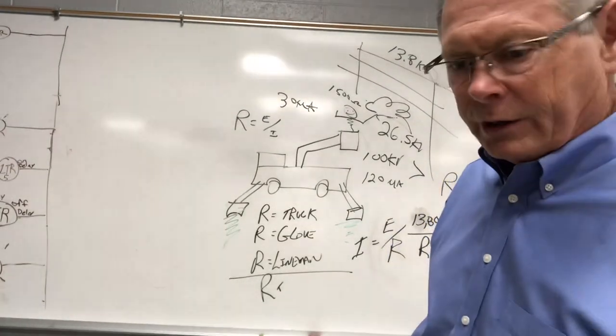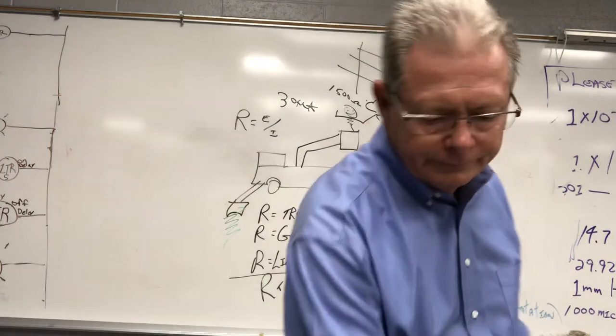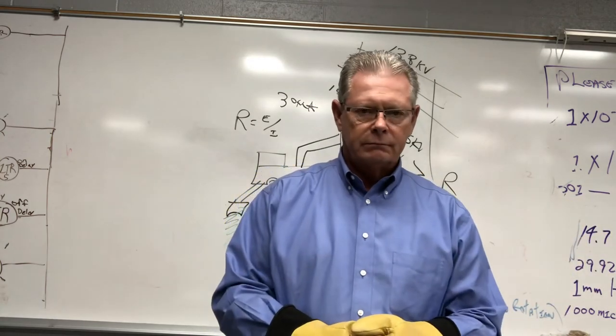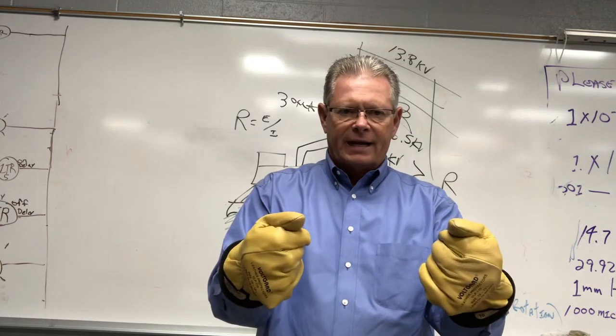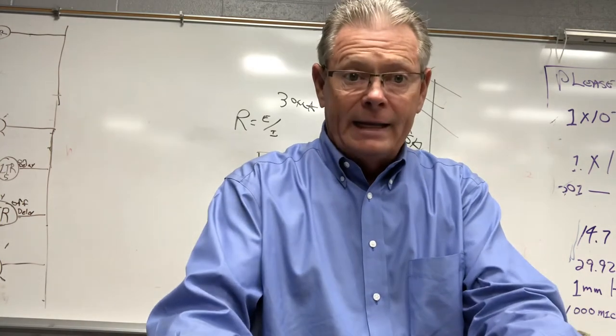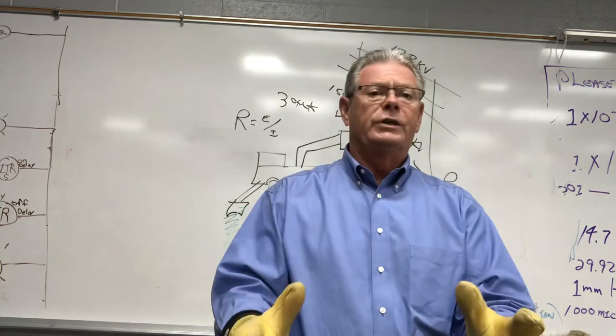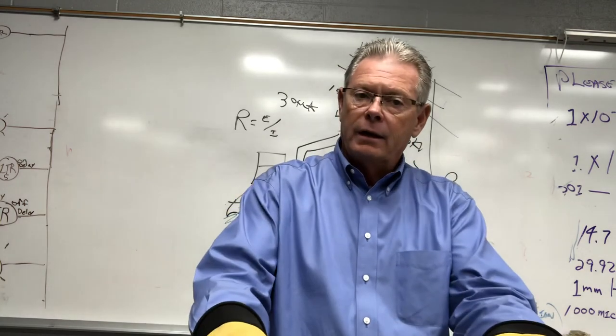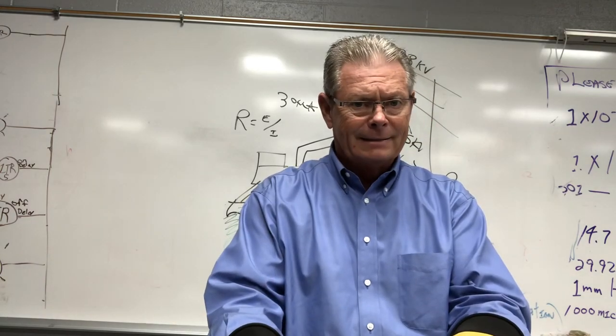Now what's that mean to us as electricians if we're not linemen? If we put our gloves on, we're saying that we're getting ready to test the circuit. So we're testing a circuit, we have our meter leads in our hands. There's no perfect insulator. So when we touch 480, and you're going to do a lot of testing on 480, that is the most predominant voltage out there for motors in the industry. Then right now you know, based on what we've talked about, there will be current flowing through your body. You might not feel it.